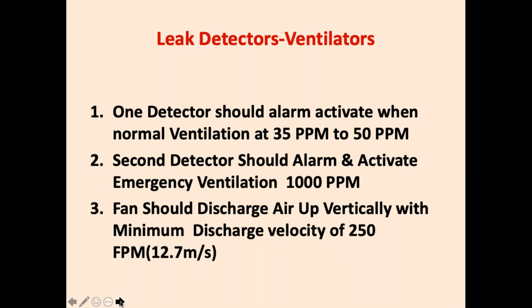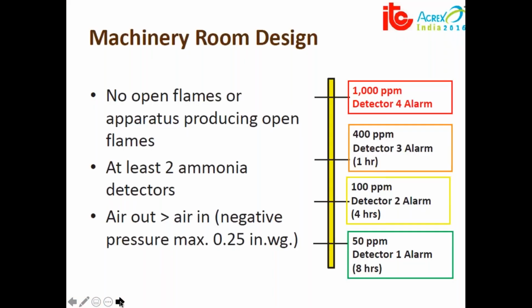This is important: how to select the fan. These are the set points of the sensors, various set points. I will not read them out. Air outlet, negative pressure. Many times, if it is a totally closed plant room, many people prefer negative pressure in the machine room, because then the chance of ammonia leaking outside the machine room is nil. It is an expensive process to build a machine room with negative pressure, but that is possible.